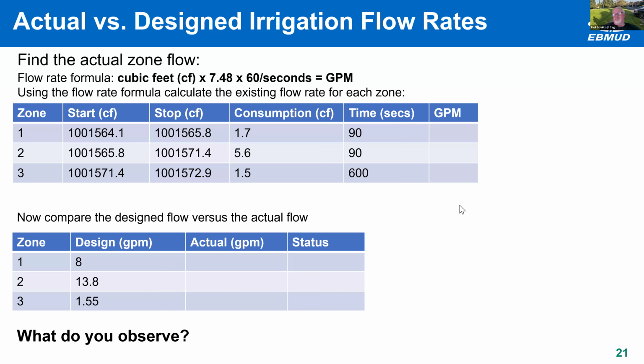I have 8.477333 gallons per minute. Great. Yeah, Paul is correct. We're going to go ahead and round it up, but that is correct. We got that by taking our consumption in cubic feet, that 1.7, multiplying it by our gallons conversion factor, which was 7.48, multiplying that by 60, and then dividing by the time, which was 90 seconds. That gave us 8.477, which we rounded up to 8.5.